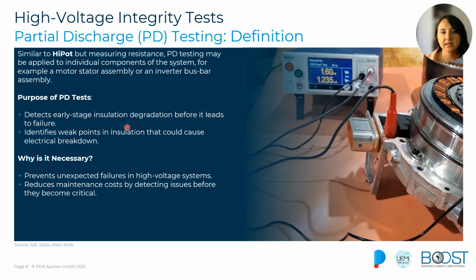The purpose of this test is then to identify those weak spots and those micro cracks or voids that with the traditional HiPot test we might not catch because they are very insignificant at this point. It is very necessary because over time and because of the repetitive activity that we are doing with the battery, those micro cracks or voids can lead to unexpected breakdowns. So this test can be applied in general to test individual parts or to test the entire system and to detect those failures early on. Based on these tests, we can, for instance, schedule maintenance or replace parts proactively, reducing the downtime of our system and lowering the long-term cost of it.